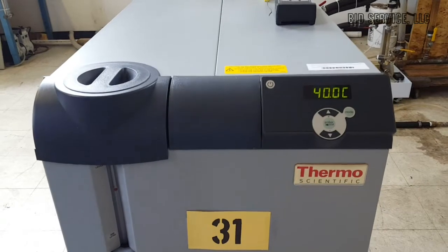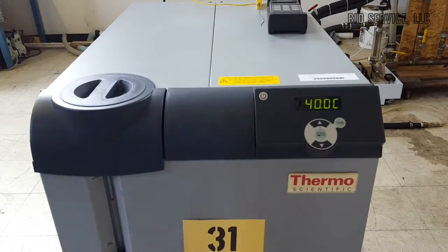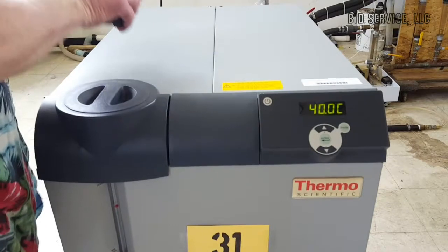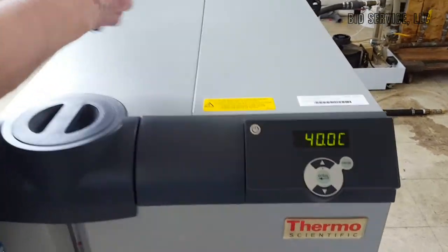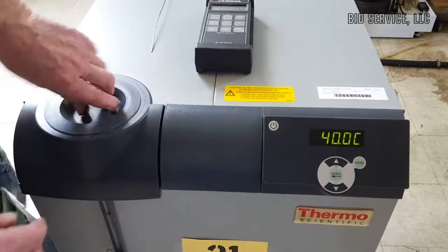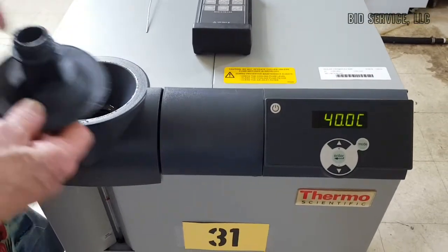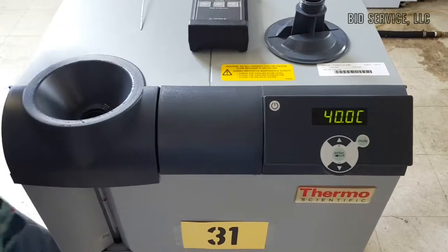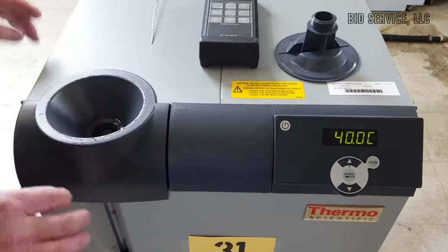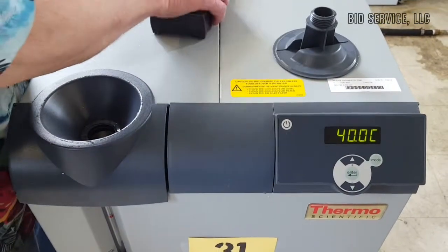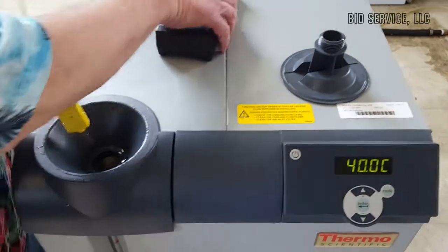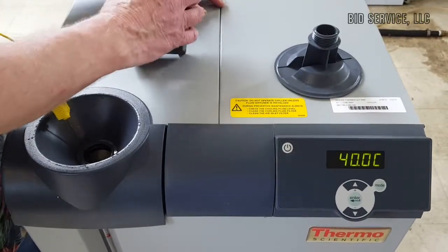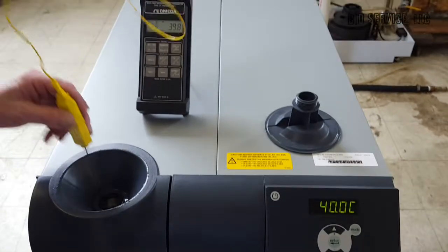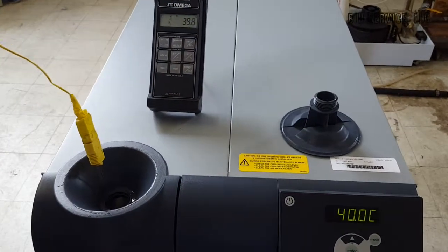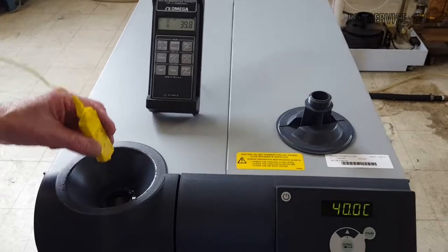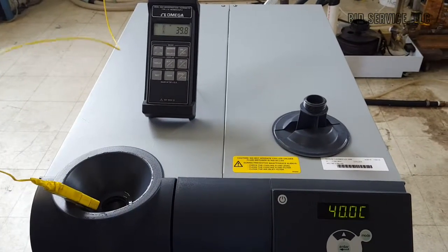Up to our maximum temperature of 40 degrees C. We have a calibrated temperature probe here that we're just going to check with real quick. Also gives me a chance to show you, this is nice. Instead of having to use a funnel, they have a funnel built right into the reservoir. So outside we're about 24 degrees. Let's see if we get here. Not bad. 39.8. So this is very good.